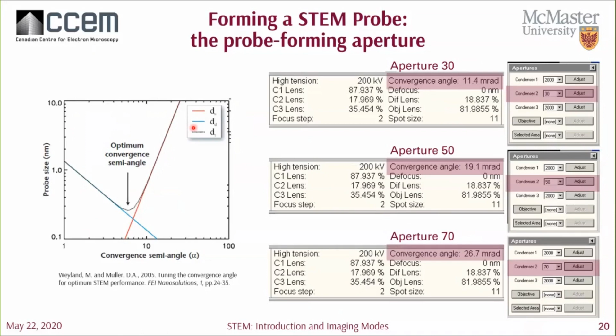Now, the final step in converging is to converge the beam into a probe on the specimen. We do that by changing the C2 lens and also the resulting C3 lens. As we increase the strength of the C2 lens, there's a further demagnification of the image between the C2 and the C3 lens, shown here. So strengthening of the C2 lens decreases the convergence angle. As shown here, increasing the strength of the C2 lens will decrease your convergence angle.